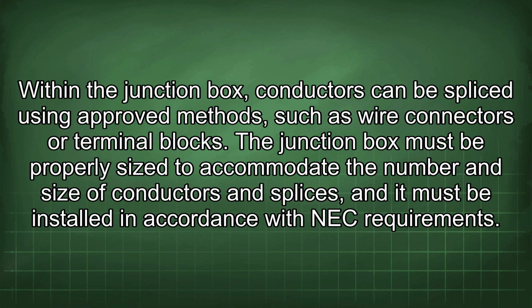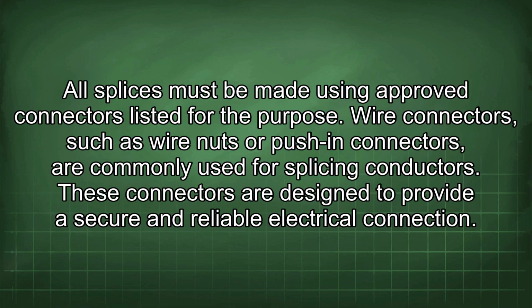Within the junction box, conductors can be spliced using approved methods, such as wire connectors or terminal blocks. The junction box must be properly sized to accommodate the number and size of conductors and splices, and it must be installed in accordance with the NEC requirements. All splices must be made using approved connectors listed for the purpose.